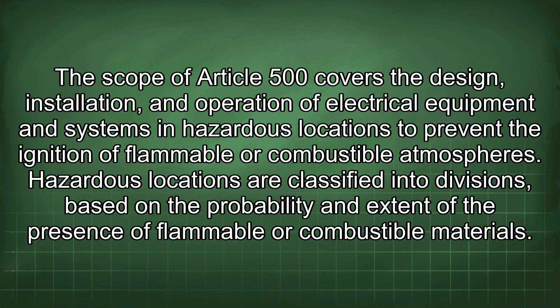Hazardous locations are classified into divisions based on the probability and extent of the presence of flammable or combustible materials. Division 1 locations are those where hazardous materials are present in sufficient quantities to produce a hazardous atmosphere under normal operating conditions. Division 2 locations are those where hazardous materials are present in sufficient quantities to produce a hazardous atmosphere only under abnormal operating conditions.